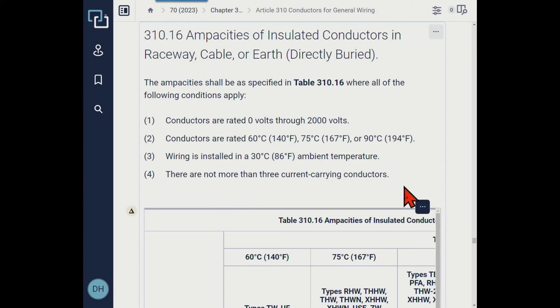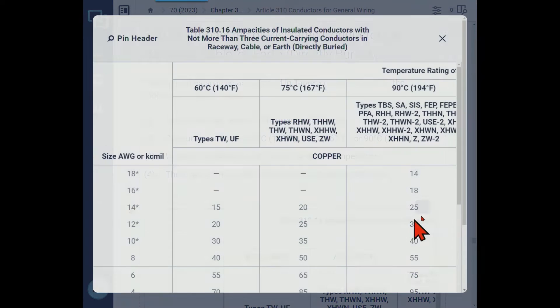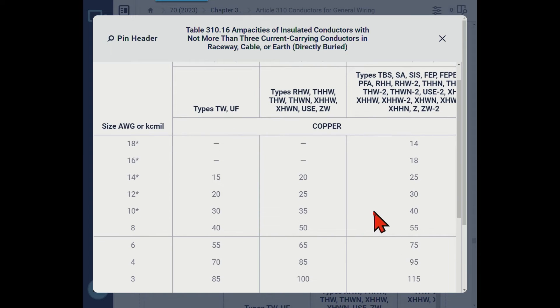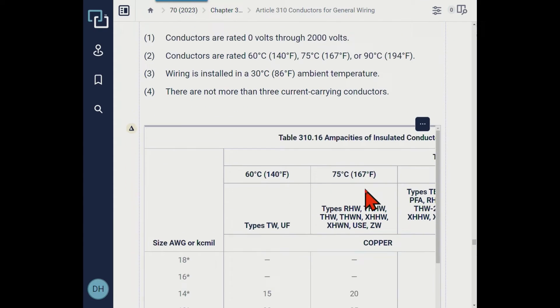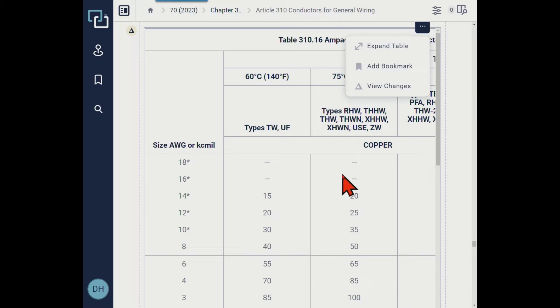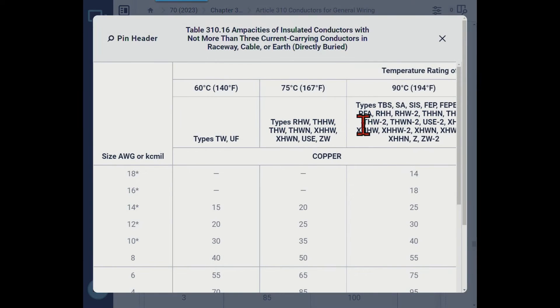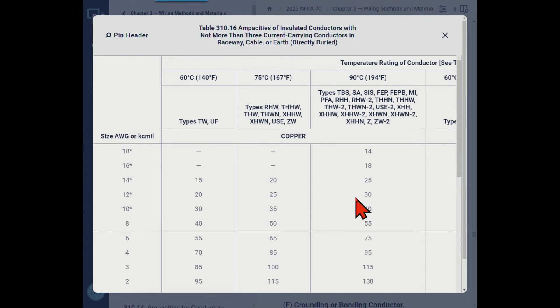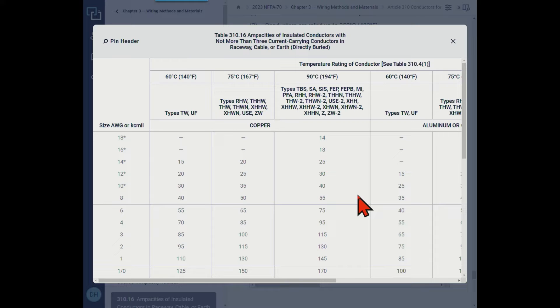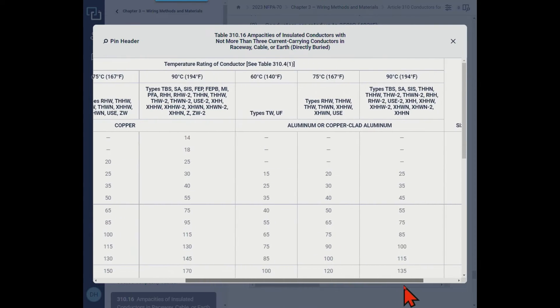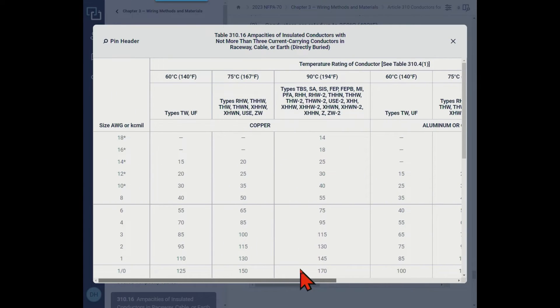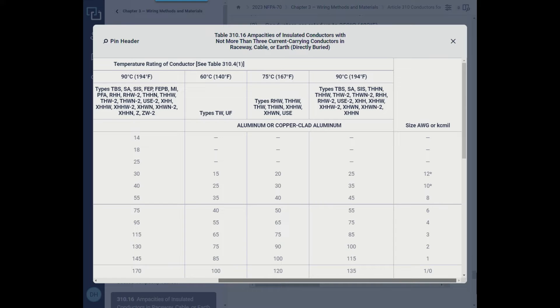Looking right into the table for 14 gauge aluminum — expanding and zooming out to get the whole table visible — at 60 degrees C for aluminum, 14 gauge: it looks like the answer is that there is no ampacity listed. So there is no ampacity for 14 gauge aluminum copper clad in Table 310.16.